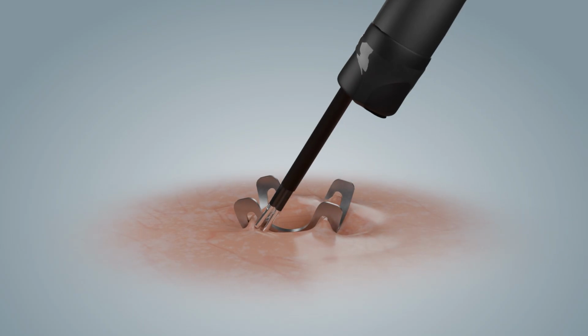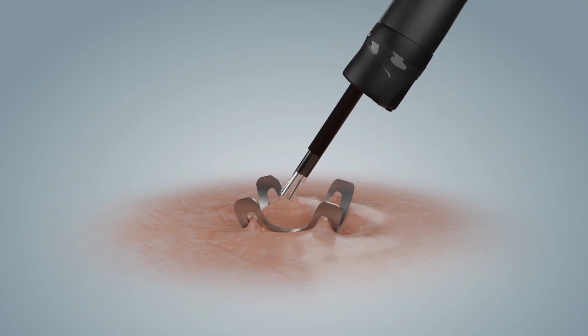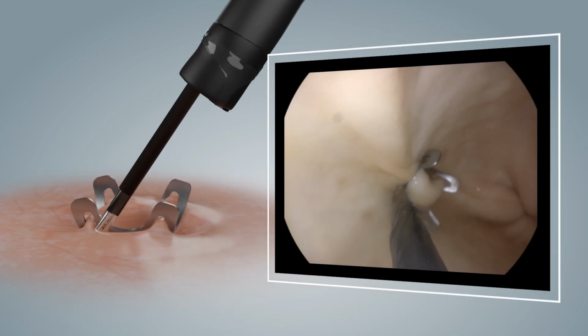A continuous audible signal confirms that all 3 tips are in full contact. An intermittent or stuttering signal means that not all 3 tips have contact. This is not sufficient for a cut. Rotate the endoscope or reposition the cutter until the tone is stable. With a continuous tone, press the foot switch once to trigger the cut.